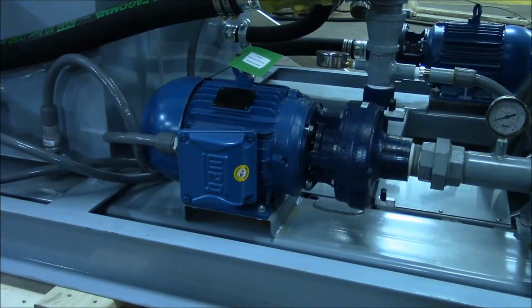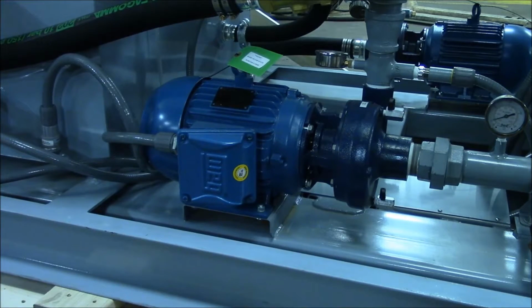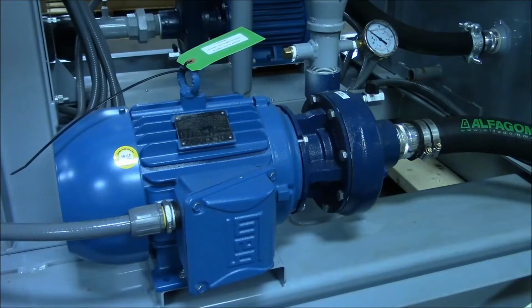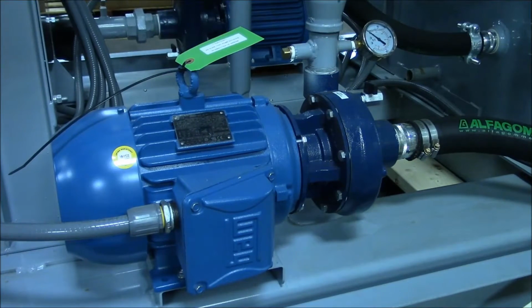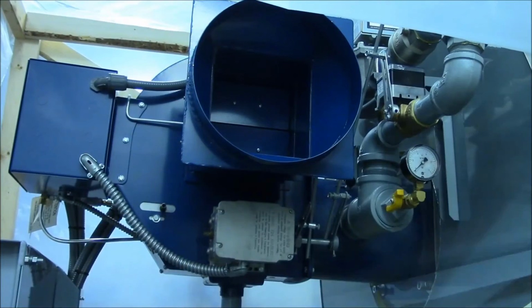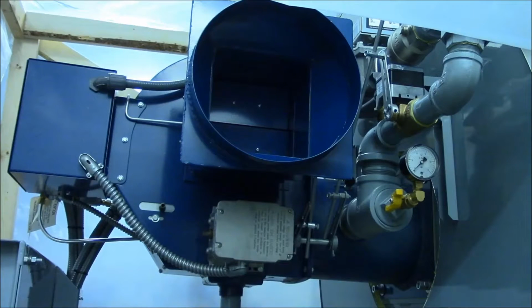The inlet pump will turn on until the proper tank level has been achieved. Then the discharge pump will turn on. The burner will turn on after water starts flowing in the coil. When the burner starts, check that the blower fan is rotating the correct direction. Refer to the machine manual for steps to change the rotation direction if it is not correct.